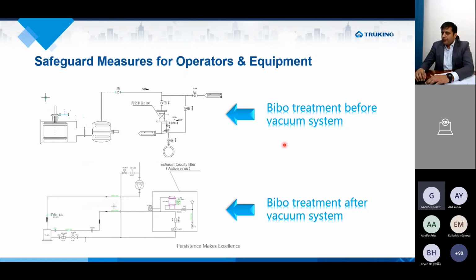So BIBO treatment can be applied two times on the vacuum system. First of all, the vacuum system is part of the lyophilizer. And this is the BIBO, put here. This is the vacuum pump. This is in a P&ID. This is the condenser isolation valve chamber of a lyophilizer, controlled by hydraulics. So at the inlet of the vacuum pump, we can add a BIBO, which acts as a barrier for anything contagious coming out into the system. And the same can be done at the outfeed of the vacuum system as well. So there are BIBOs at two critical locations that ensure no solvent and no traces of harmful vapors are released to the area, to the room.